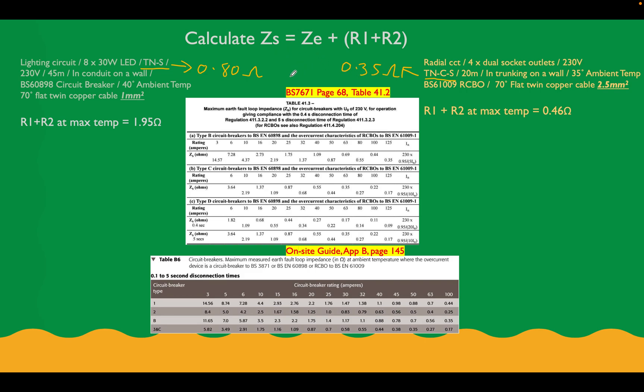Anyway, so now we know our ZE value, surely we can come down here now, and we can do these two circuits, and we can calculate our ZS. So if we know that our ZE for this side is a TNS system, so it's going to be 0.80 ohms, and we know on this side it's going to be equal to 0.35 ohms. So we know that now. Perfect.